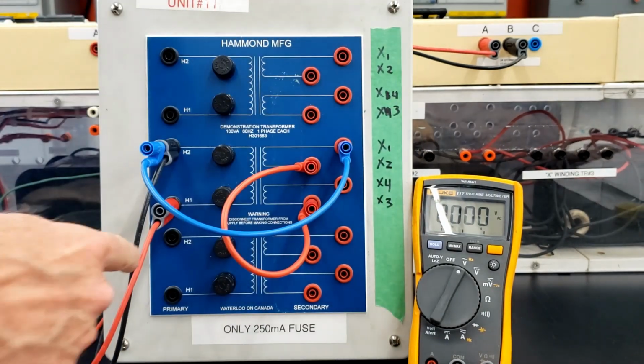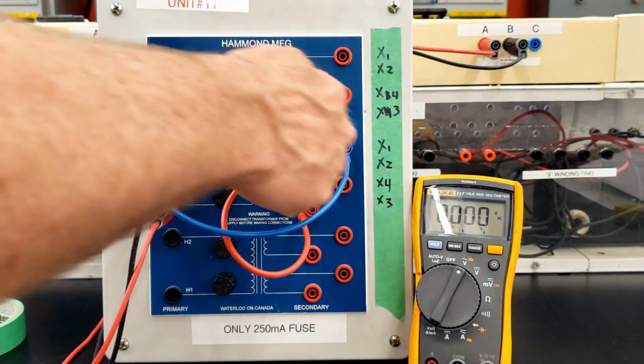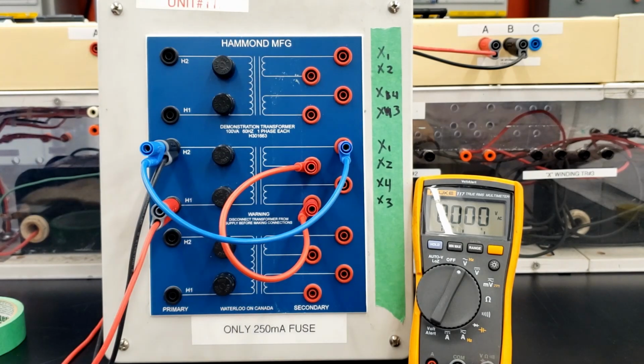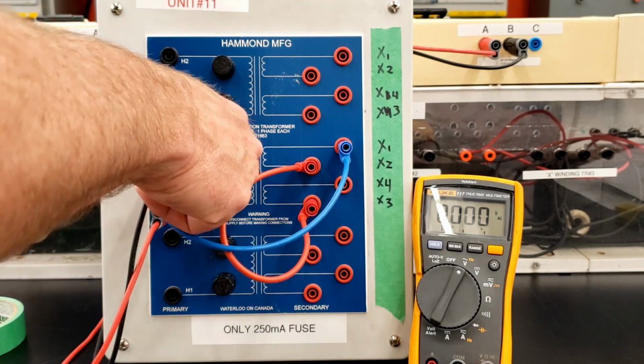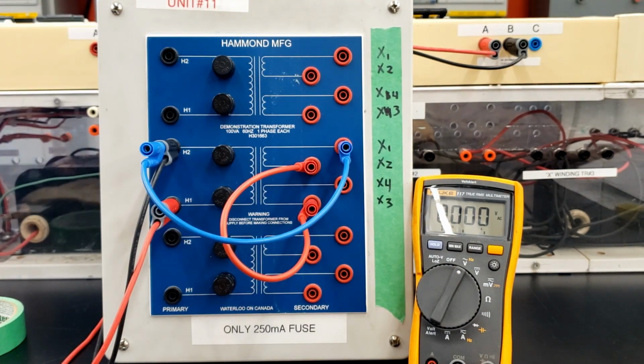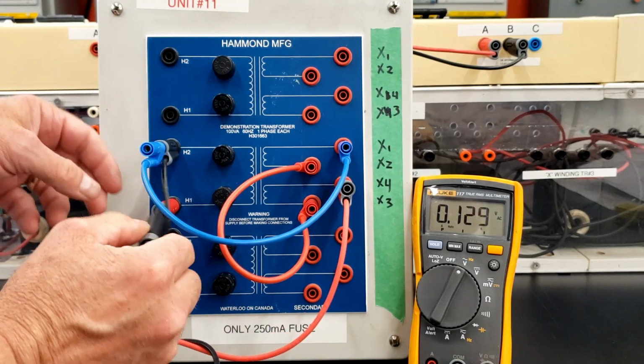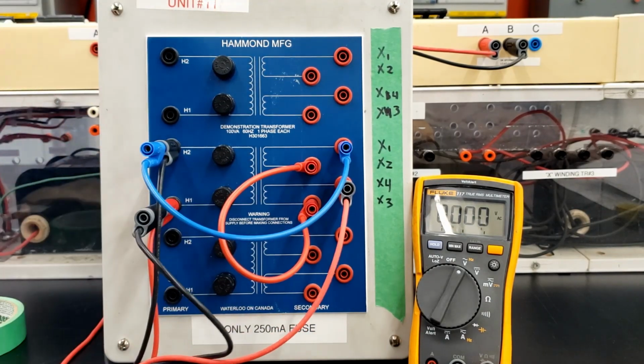I've now seriesed up this primary and all the secondary windings. I've created something similar to an auto transformer, in that there's no disconnect now between the primary and secondary. This, I believe, is my additive voltage. So now when I go between X4 and H1, those are my open connections, I should see the higher voltage being developed on the meter.